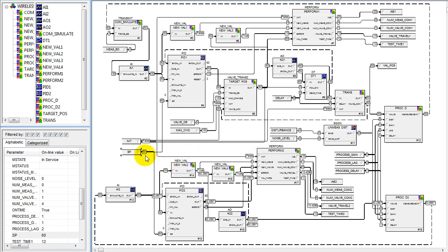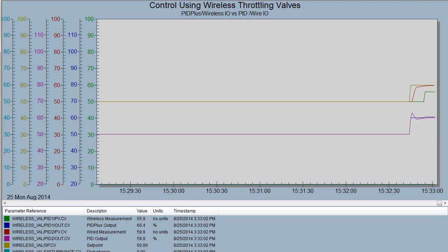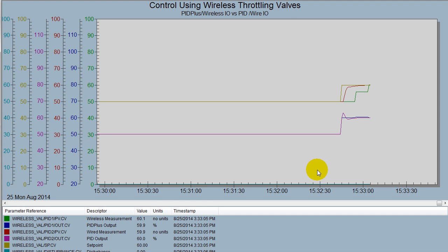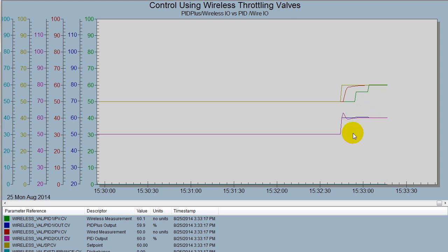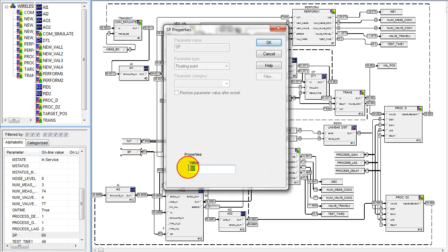In response to our setpoint change, we notice that the wireless control as well as the wired control is changing output to the valve, and the processes are reflecting that change in valve position. We can better see the dynamic response by looking at a trend. We can see that we've changed the setpoint, and in response the smooth change is the wired transmitter and PID, while the stepwise change is the wireless measurement.